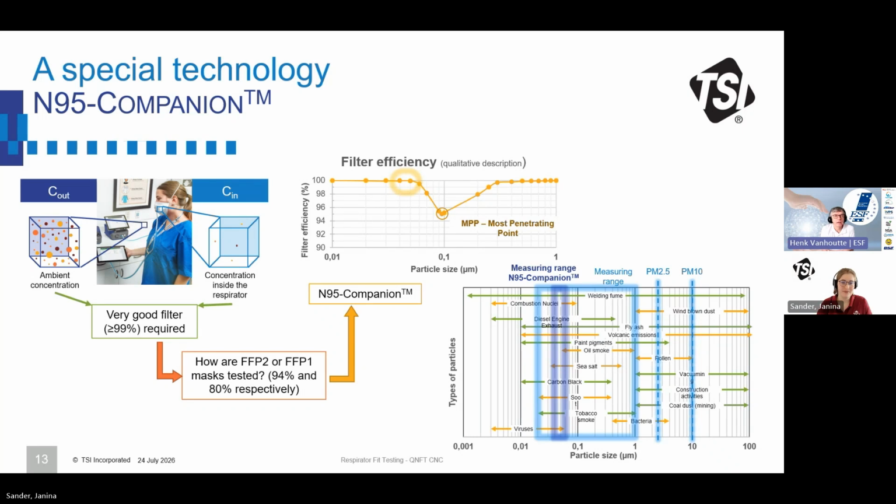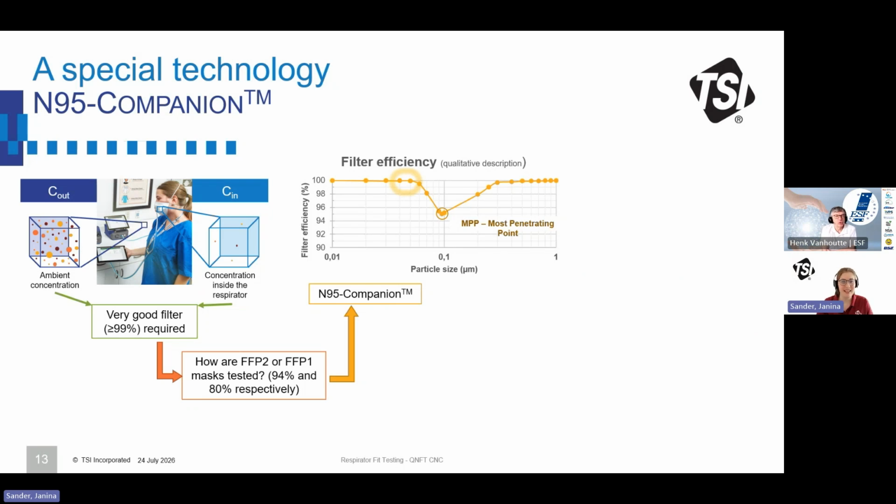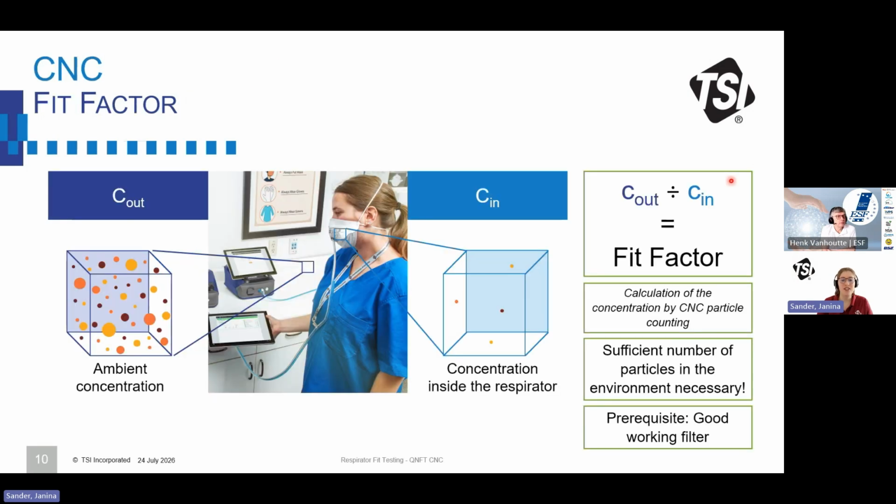Okay, and in the Q&A, I see a question: are there ever zero particles present in a CNC fit test? From a mathematical point of view, no, because if I go back to this slide here, if I would have zero particles inside my respirator, it's mathematically not possible to calculate a fit factor.